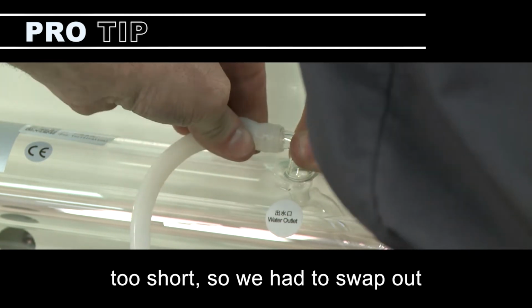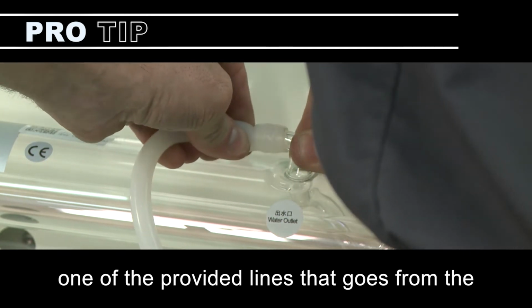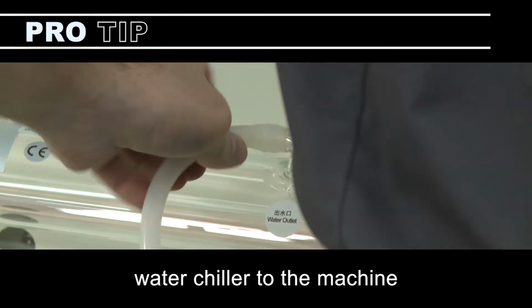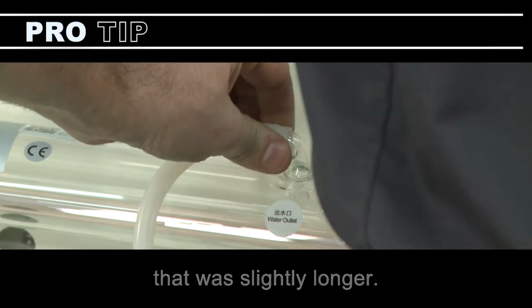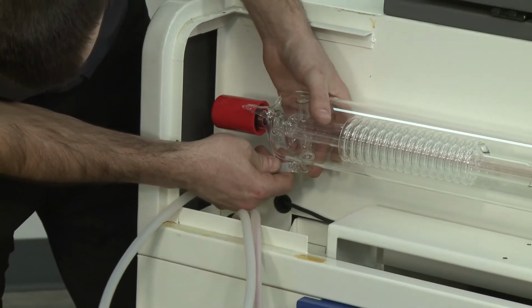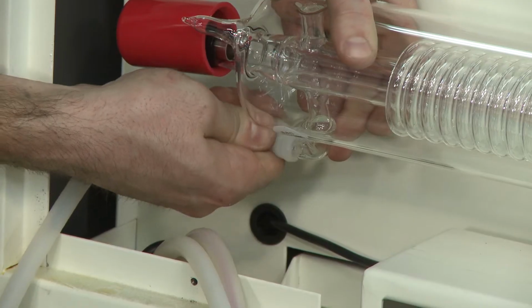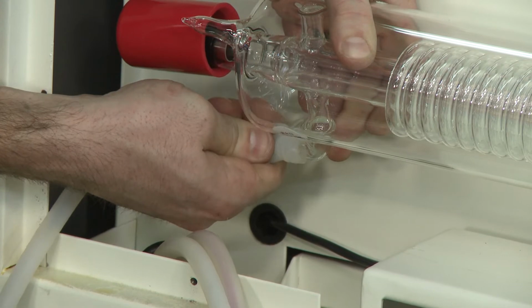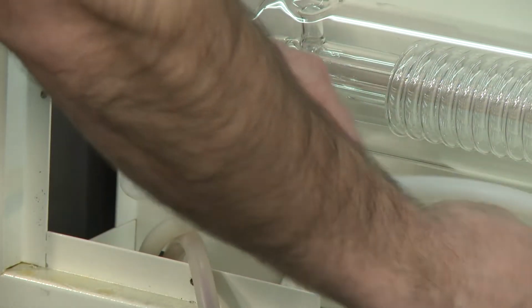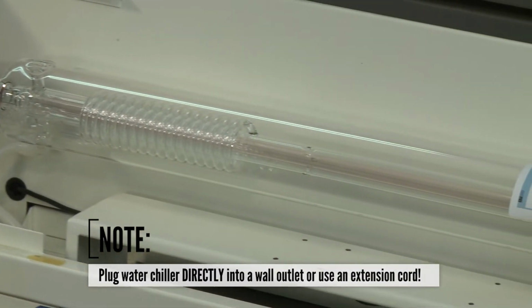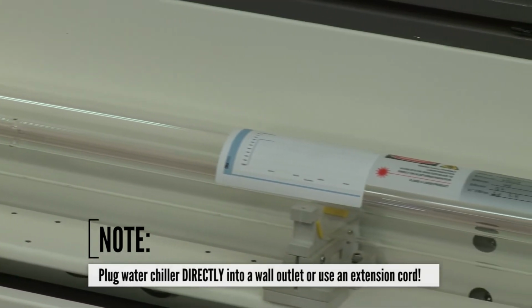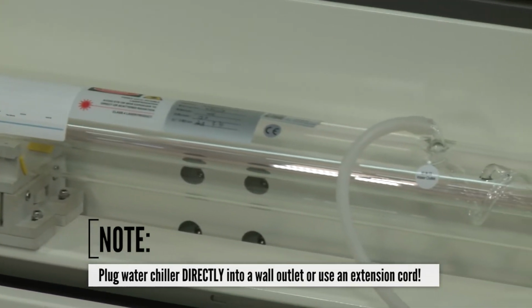And take note for customers calling in, on this machine in particular, the line from the factory that I'm installing right now was actually too short. So we had to swap out one of the provided lines that goes from the water chiller to the machine with one that was slightly longer to allow us to reach that distance. Here we're showing the water inlet pipe from the barbed fitting on the machine to the water inlet on the laser tube. Once you are ready to begin filling the laser tube with water, plug the water chiller directly into the wall or use an extension cord.